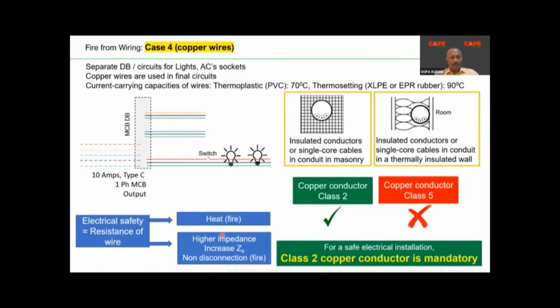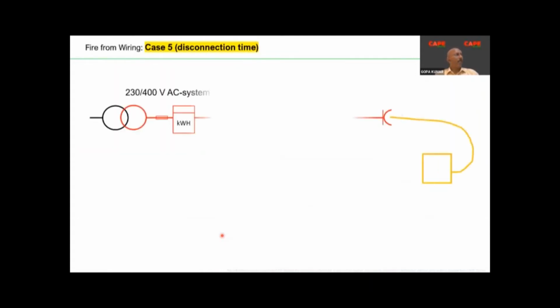Now, why I stress this point more is that copper wires with class 2 conductors are not generally available in the market. If you want to buy copper wire with class 2 copper, which is the one recommended in the standard, in most of the shops it's not available. So I would recommend the participants, after the program, to call your wire supplier and check what kind of wires you are using. You are supposed to use class 2 copper wire.